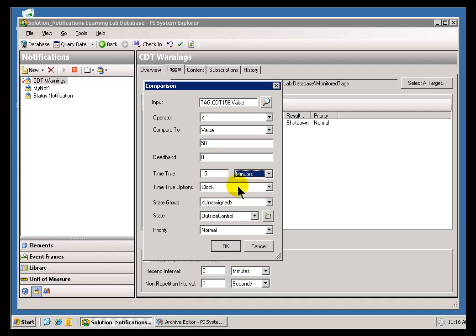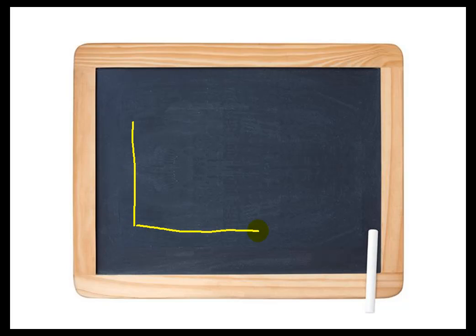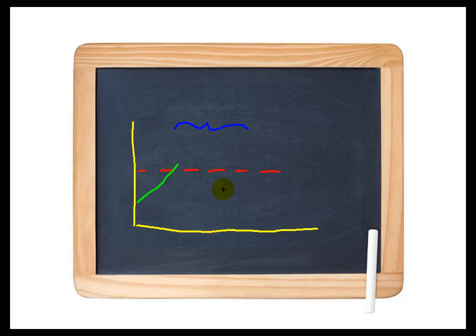For Time True, we have a couple of options that need to be explained in some detail. We have Clock versus Natural — the default is Clock. When we've set up Time True, we're essentially saying, here's our Timeline, and we've got a Tag with an Alarm Limit right about here. As our Values come in and the value increases, once it crosses this point, we want some interval of Time to go by before we actually send an Alarm.